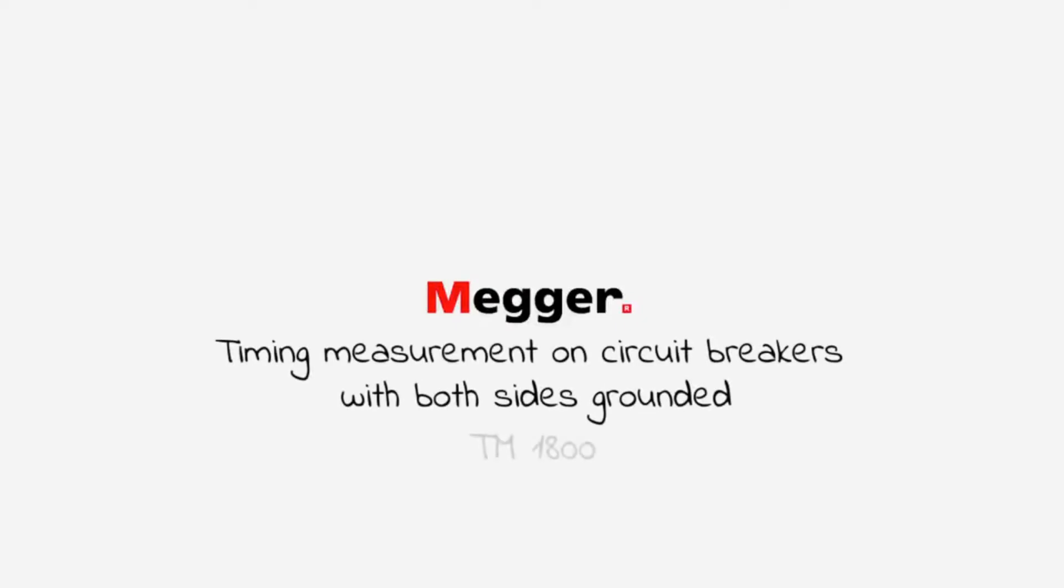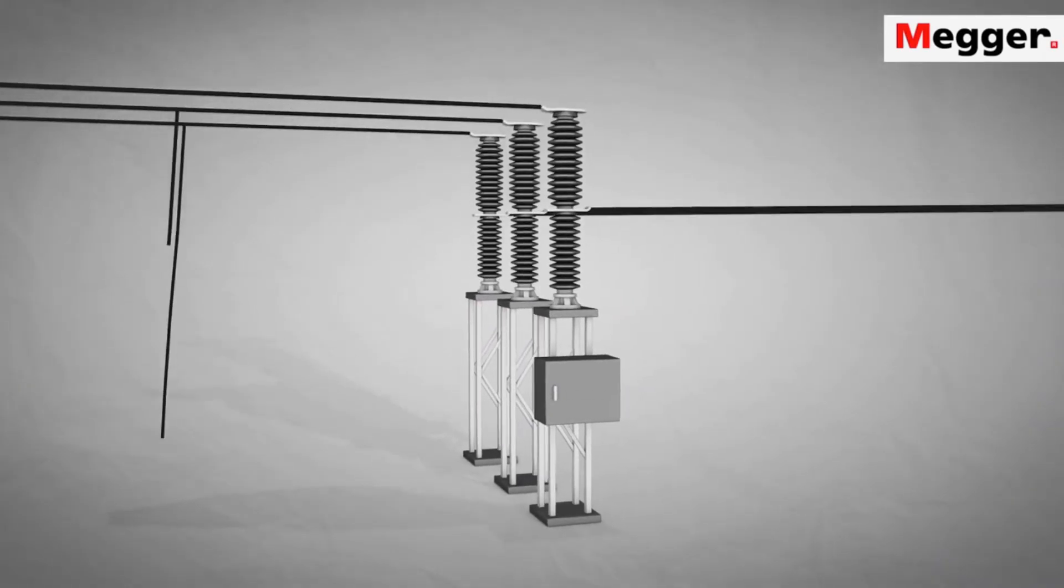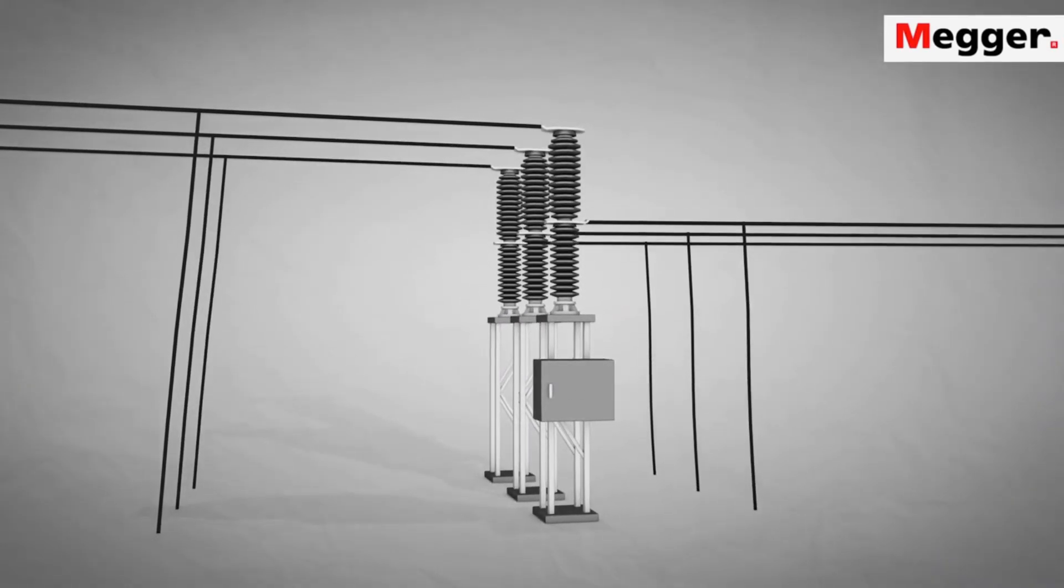Timing measurement on circuit breakers with both sides grounded. According to international safety standards, a circuit breaker should be grounded on both sides while work is performed.